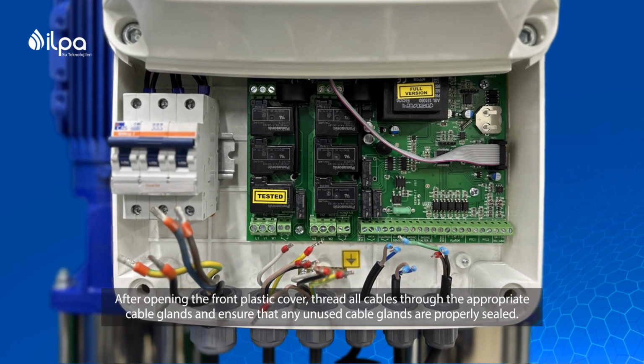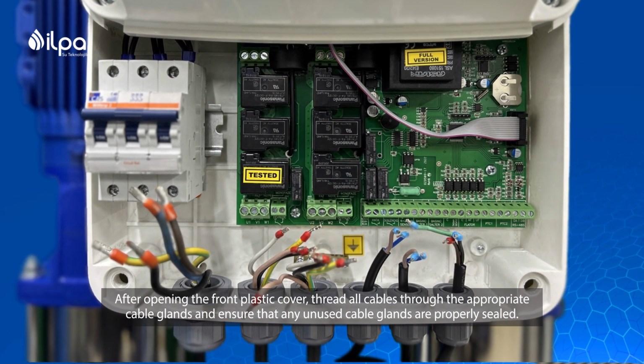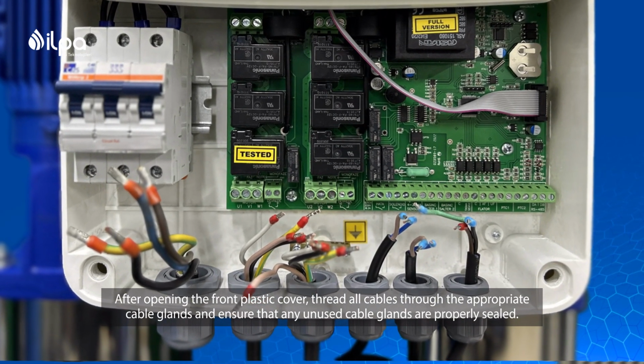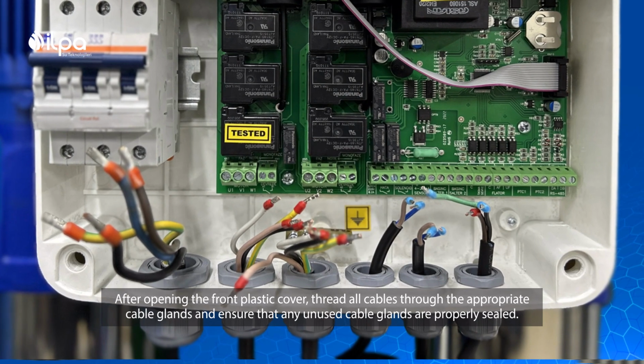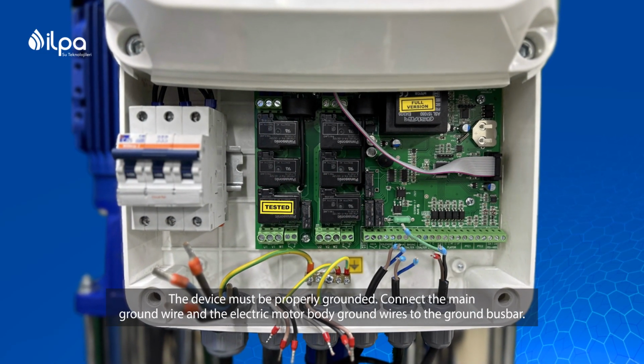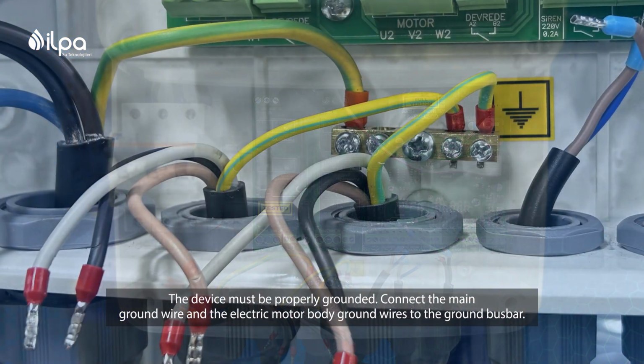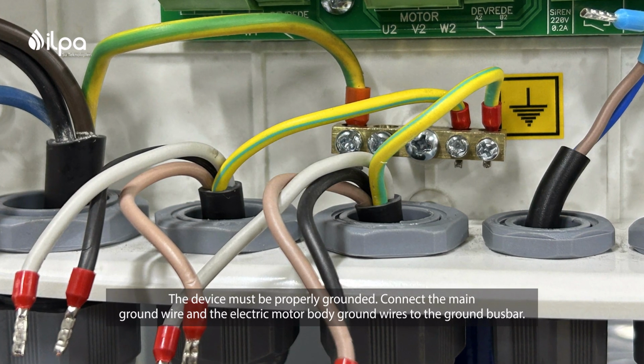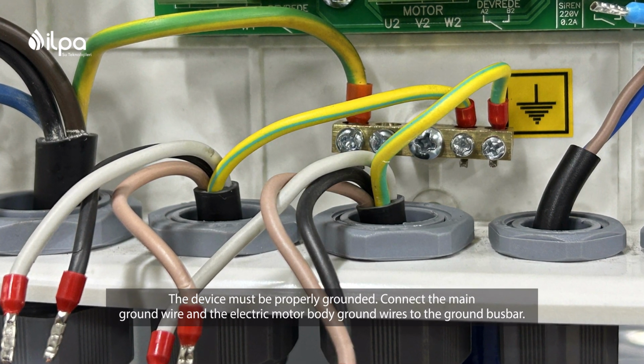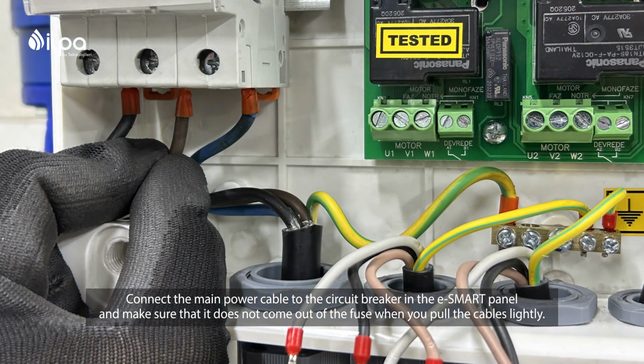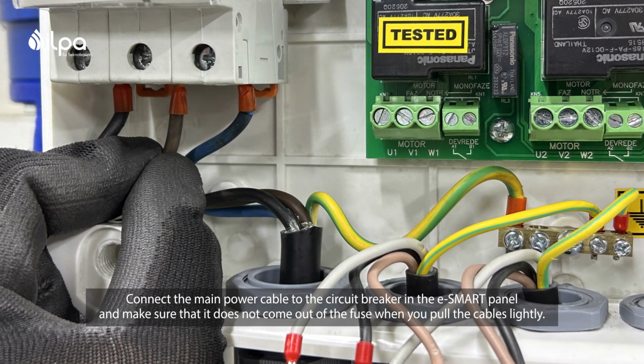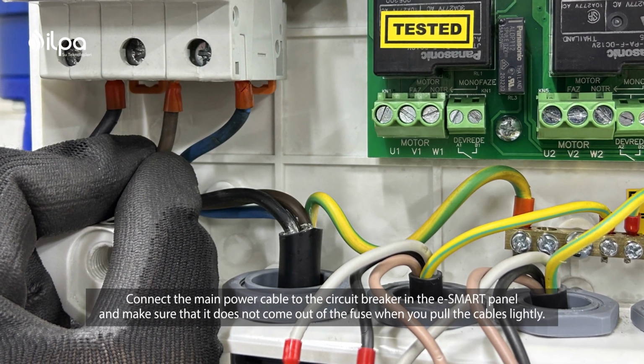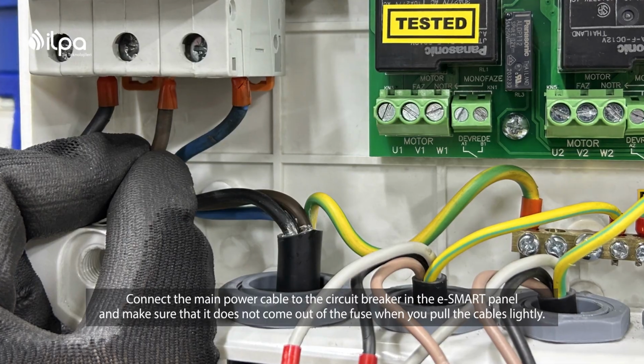After opening the front plastic cover, thread all cables through the appropriate cable glands and ensure that any unused cable glands are properly sealed. The device must be properly grounded. Connect the main ground wire and the electric motor body ground wires to the ground bus bar. Connect the main power cable to the circuit breaker in the eSmart panel and make sure that it does not come out of the fuse when you pull the cables lightly.